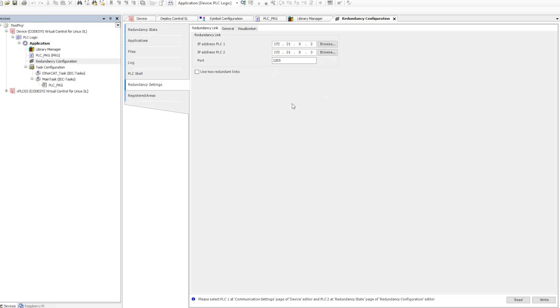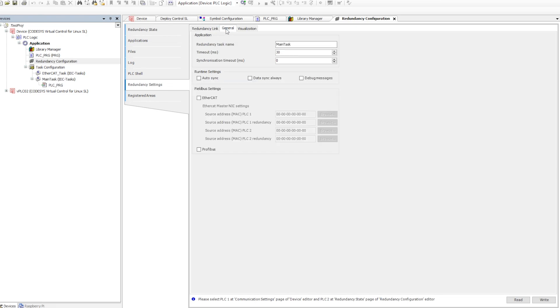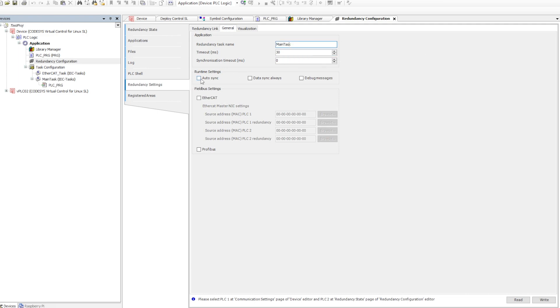Once this is configured, we'll keep the port number at 1205 as the default — it can be changed based on need. Now we go to 'General'. Sometimes you will not see the task name there, so we use the main task or whichever task you have configured, and we set it to auto sync. Auto sync means it will synchronize automatically and keep data in sync always.